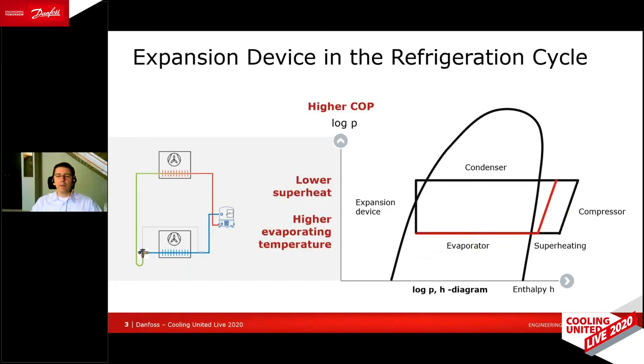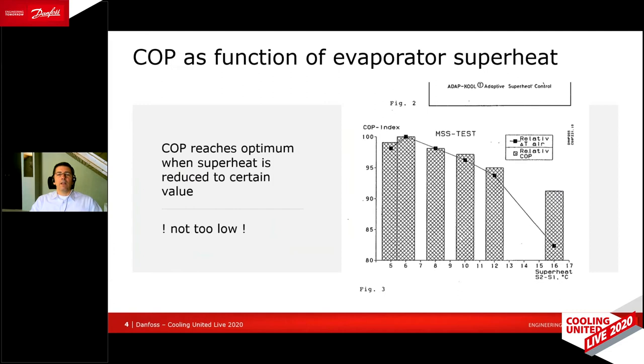We can reduce the superheat setting quite often. When we do that, we get a little bit of an increase in the evaporating temperature, and that helps us to have a more efficient system. The question is, of course, how much can we reduce the superheat?